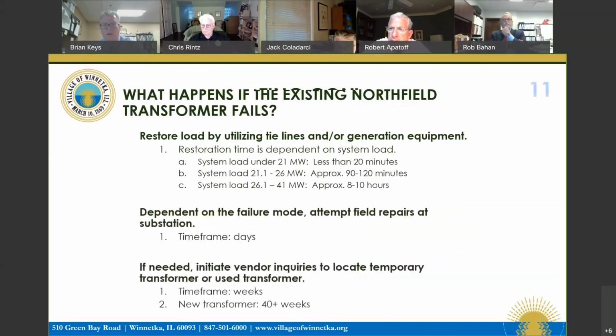Next slide. Again, this is just a restatement: 21 to 26 megawatts is 90 to 120 minutes, and beyond that we're looking at bringing the plant up. A transformer failure could go either way. It could be repaired in days, or if it's catastrophic, we're looking at several weeks to a year. We'd start by looking for an emergency portable substation and/or a used transformer, and a new transformer purchase is like 40 plus weeks after drawing approval. So this is not an item that's commonly available, though there are used markets for used substation transformers.